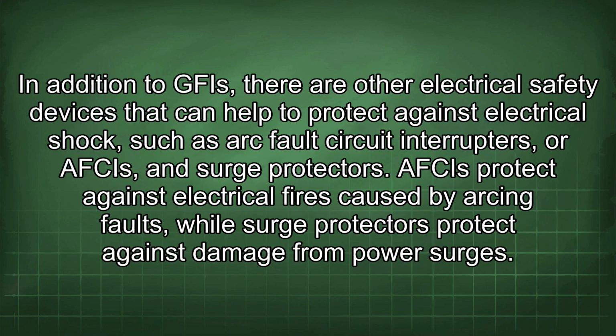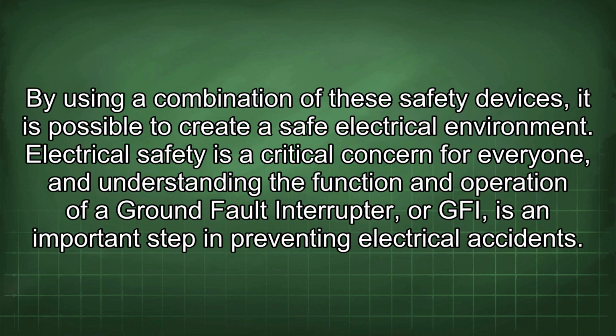In addition to GFI, there are other electrical safety devices that can help to protect against electrical shock, such as arc fault circuit interrupters, or AFCIs, and surge protectors. AFCIs protect against electrical fires caused by arcing faults, while surge protectors protect against damage from power surges. By using a combination of these safety devices, it is possible to create a safe electrical environment.